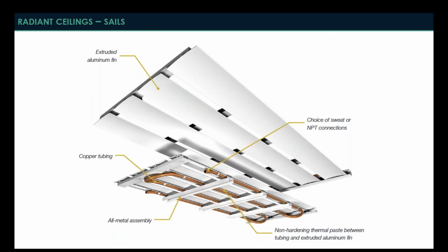Another type of radiant ceiling panel is what is known as a radiant sail, or oftentimes they are referred to as chilled sails, but they can also do heating as well. And the primary benefit of a system like this is that the increase in surface area of the panel itself, because it is using arched or rounded panels, allows for a greater capacity per square foot of ceiling space. So sometimes when you need a little bit more capacity than perhaps a modular or linear panel can give you, a radiant sail can be a good option.